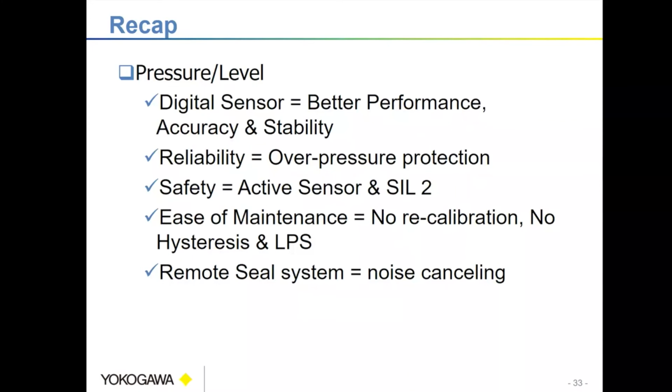Yeah, and one more comment. It's not all welded as Hastelloy. Our diaphragm is Hastelloy. That's our standard material. And the reason we did that when we released the series was, you probably noticed over the years the transmitters have gotten smaller, and as a result, the capsules get smaller, so the diaphragms get smaller. So to keep a spring rate for sensitivity for passing these smaller pressures, the diaphragms become thinner. So Yokogawa upgraded the diaphragm material from stainless to Hastelloy, right? Because Hastelloy has better resistance properties over stainless in most applications. So that was a step to extend the life of these transmitters so they will be as robust and as long lasting as the 25-pound ones you bought back in the 60s and 70s, right?